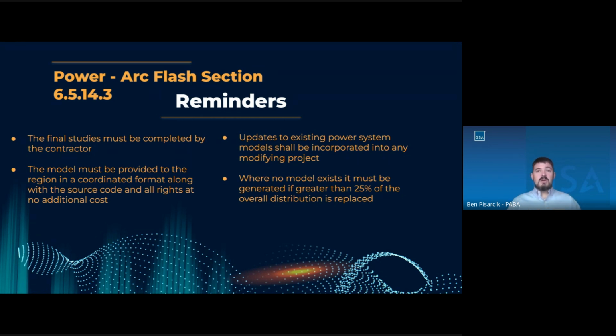We receive those models. We're able to open them up. We don't typically do the studies ourselves, but we often open them up and look to see how they were done, if they were done correctly. And we can also pass that along to a new contractor that may be doing an update to the system, which is very important as opposed to having that new contractor have to go back and recreate the model, which is extremely costly and time consuming.